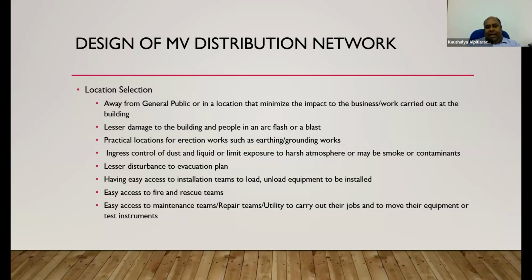Location selection. Now you saw how dangerous that arc flash was, and so we need to locate this medium voltage equipment away from the general public for more safety, or in a location that minimizes the impact to the business or the work carried out at the building, as well as people inside the building, and lesser damage to the building and people during an arc flash or a blast. Because of the high potential, a blast can happen, and that's going to be very serious.